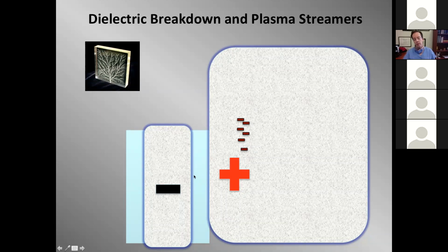It'll destroy the molecular integrity of what was left of the insulation and create a plasma, a through and through plasma arc, and blow the circuit. Now, luckily, most defibrillators have a way of detecting that and diverting all the amperage. But this is basically a 2 ohm or less bridge, so you're delivering all that energy right to the can, and you'll blow the circuits up, which is what happened in that case.